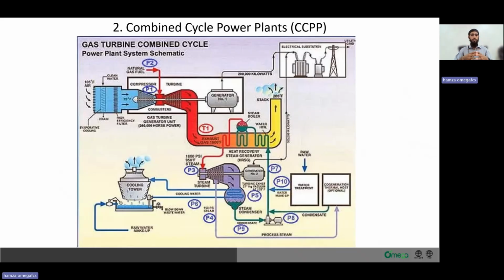Now, a heat recovery steam generator captures the waste heat from the gas turbine's exhaust. This heat is used to generate steam from water, increasing the overall efficiency of the plant. So when this steam is introduced to the turbine, we need a steam turbine. The steam produced in the heat recovery steam generators is directed to a steam turbine. This turbine, like the gas turbine, is connected to a generator, producing additional electricity. We have other control and electrical systems to go along with this, but the main components are the gas turbine, the steam turbine, and the heat recovery steam generators.